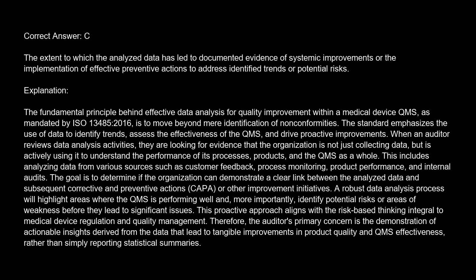The standard emphasizes the use of data to identify trends, assess the effectiveness of the QMS, and drive proactive improvements. When an auditor reviews data analysis activities, they are looking for evidence that the organization is not just collecting data, but is actively using it to understand the performance of its processes, products, and the QMS as a whole. This includes analyzing data from various sources such as customer feedback, process monitoring, product performance, and internal audits. The goal is to determine if the organization can demonstrate a clear link between the analyzed data and subsequent corrective and preventive actions, CAPA, or other improvement initiatives.